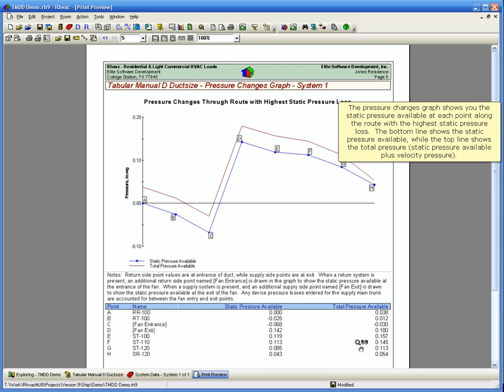The Pressure Changes graph shows you the static pressure available at each point along the route with the highest static pressure loss. The bottom line shows the static pressure available, while the top line shows the total pressure. Static pressure available plus velocity pressure.